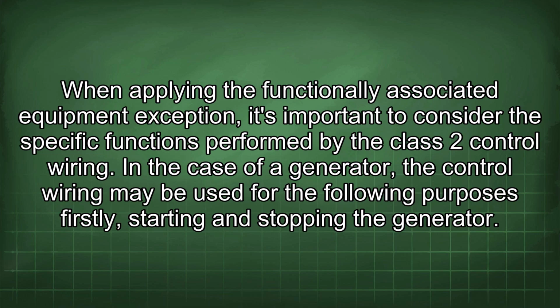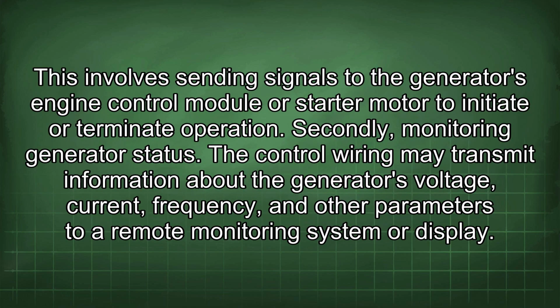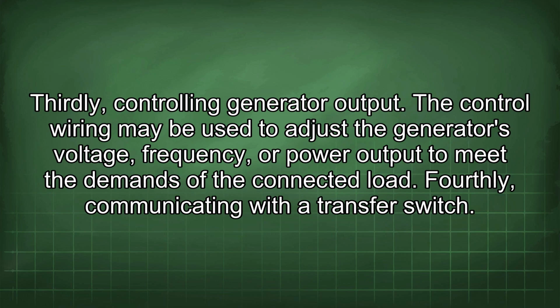When applying the functionally associated equipment exception, it's important to consider the specific functions performed by the Class 2 control wiring. In the case of a generator, the control wiring may be used for the following purposes. Firstly, starting and stopping the generator. This involves sending signals to the generator's engine control module or starter motor to initiate or terminate operation. Secondly, monitoring generator status. The control wiring may transmit information about the generator's voltage, current, frequency, and other parameters to a remote monitoring system or display. Thirdly, controlling generator output. The control wiring may be used to adjust the generator's voltage, frequency, or power output to meet the demands of the connected load.